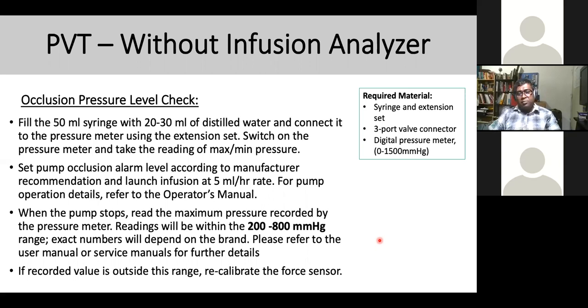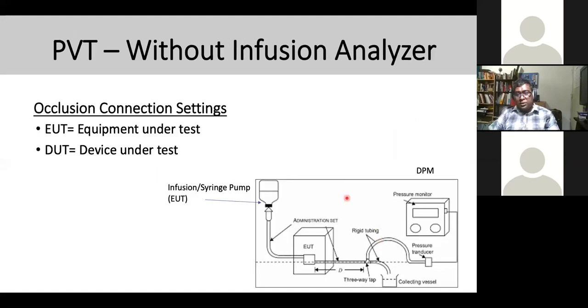This is where the reading range you're going to see. So when the pump stops and the occlusion alarm is there, you will capture the reading actually with the digital pressure meter. And the connection should be something like this. So these are for the infusion device. This is how you connect the line. So from the infusion fluid going to the EUT or DUT, equipment under test or device under test, the term we use. So these are the syringe pump or infusion pump, and you got three line tubing going to the pressure meter. So when you get an occlusion alarm on the infusion or syringe pump, you're going to see a reading of pressure on the digital meter.